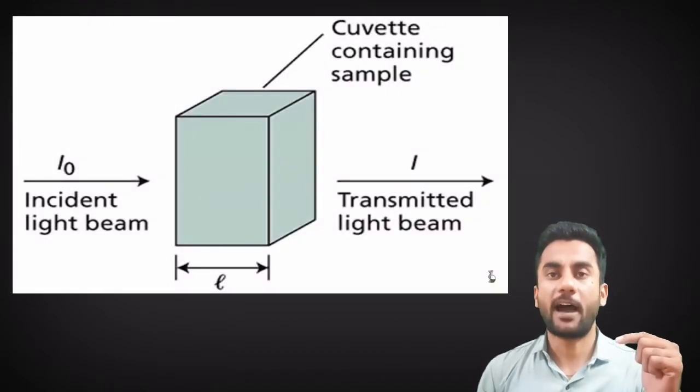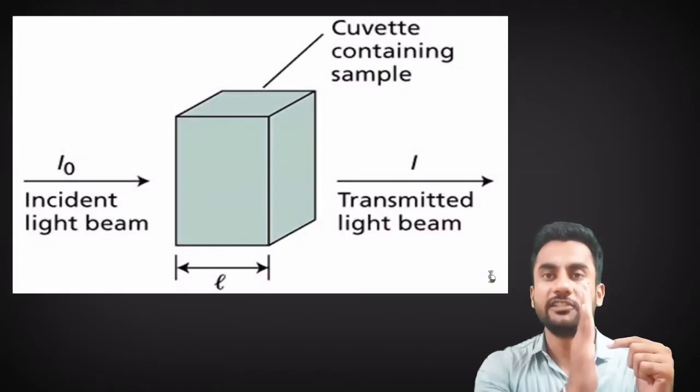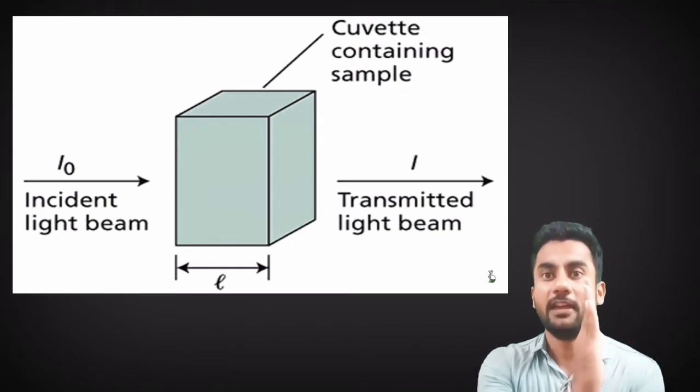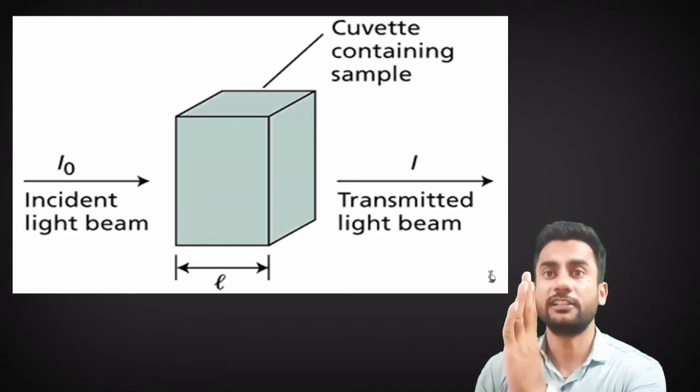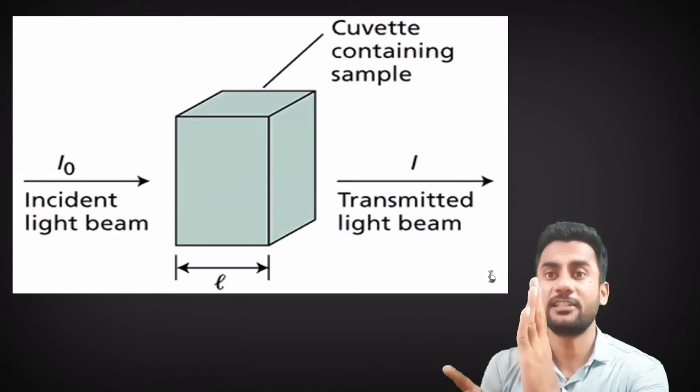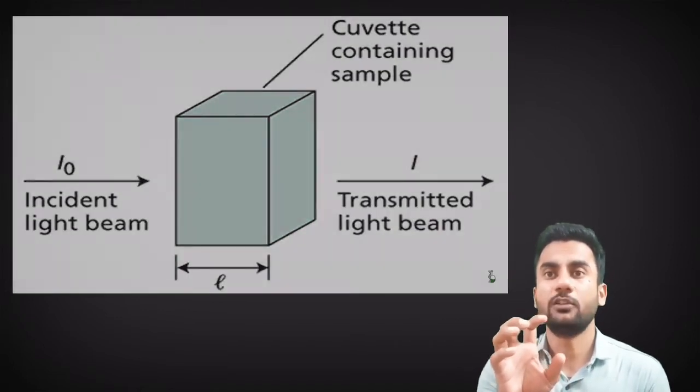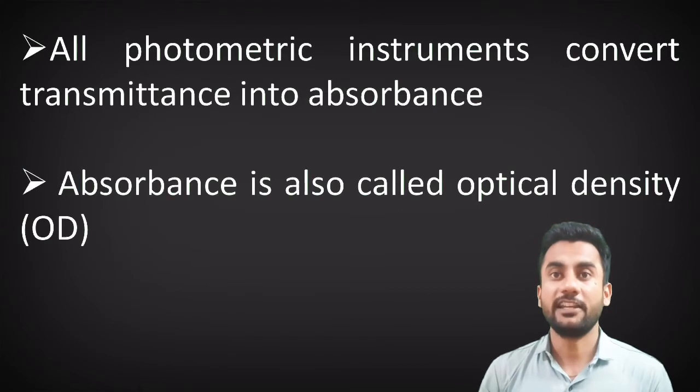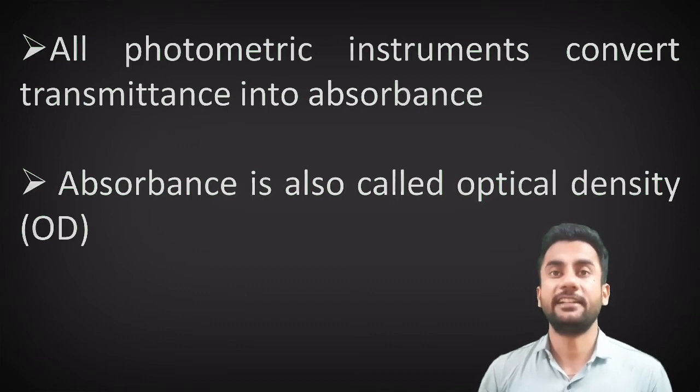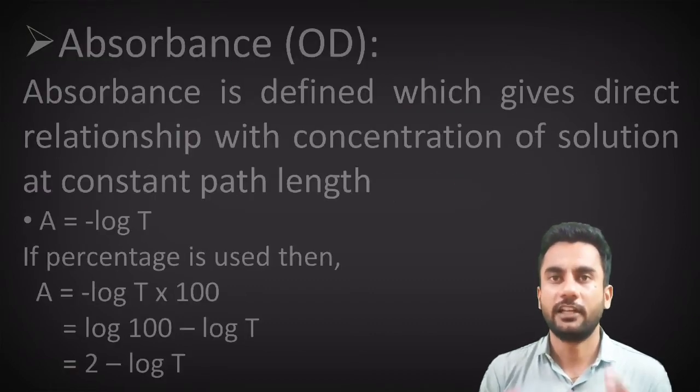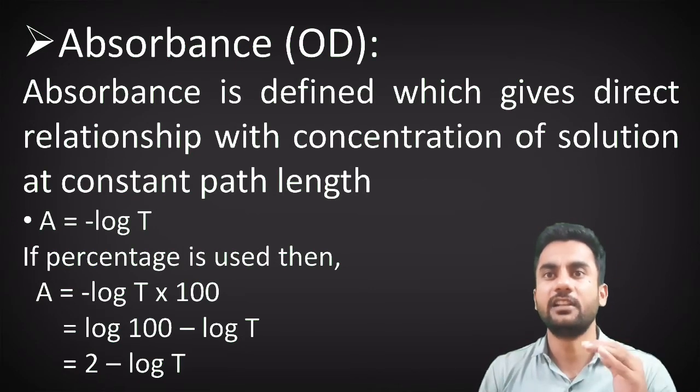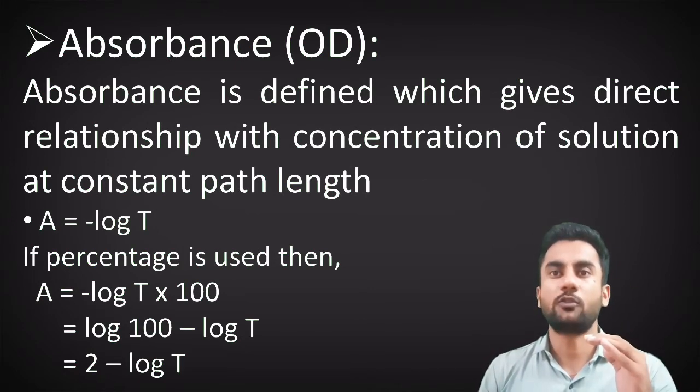When the incident light beam of I₀ intensity is allowed to incident on one surface of the cuvette containing sample having length L, then from another surface of the cuvette, the transmitted light beam is transmitted. And due to absorbance, always intensity I is less than I₀. The colorimeter is a photometric instrument, and all photometric instruments convert transmittance into absorbance. The absorbance is also called optical density.